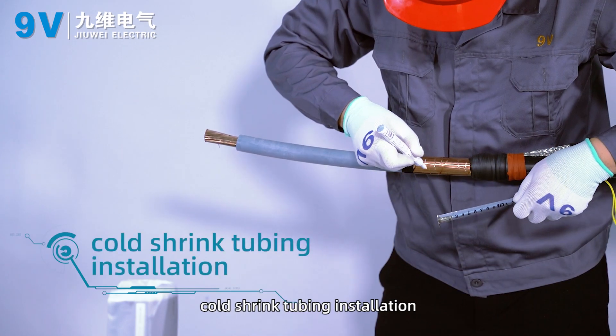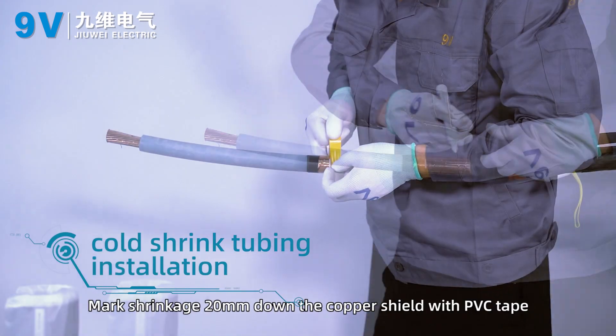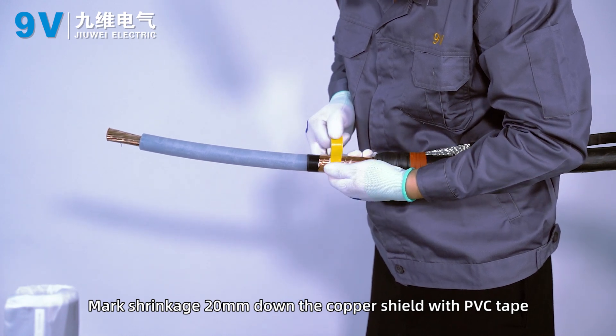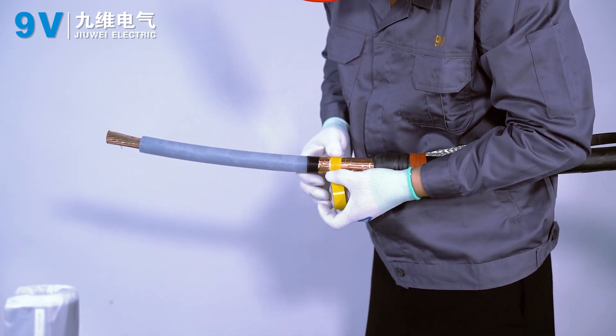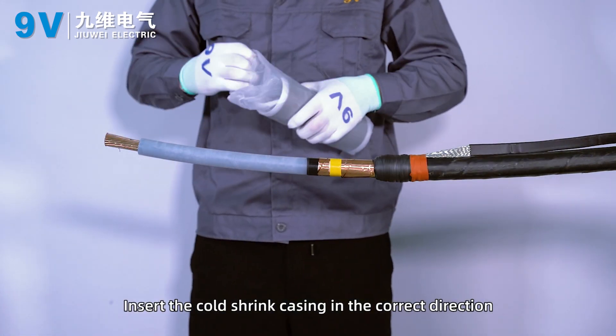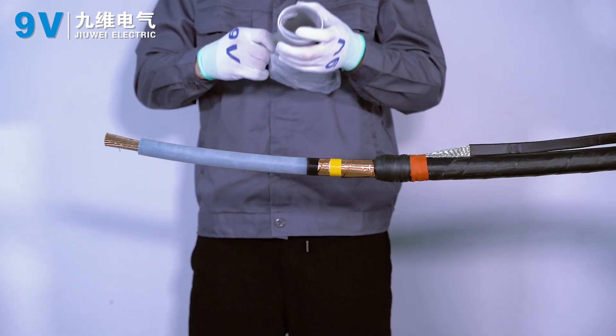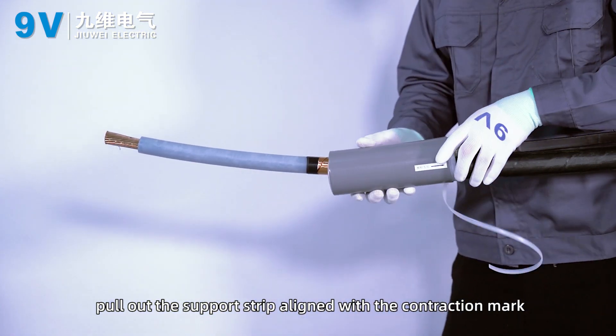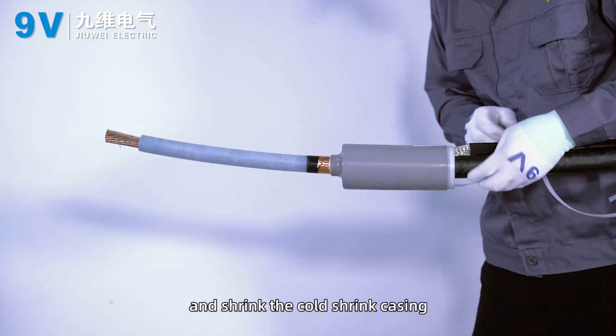Cold shrink tubing installation. Mark 20 mm down the copper shield with PVC tape as the shrinkage reference. Insert the cold shrink casing in the correct direction, align it with the contraction mark, and shrink the cold shrink casing.